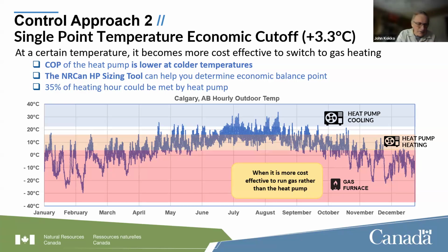we were talking about this a little before the seminar started, but Alberta has very complicated energy pricing, and it changes continuously. So I've tried to use an average over the year and said the price of electricity is about 2.5 or a little bit more, 2.8 times more than gas on average over the year. So that means once my COP drops below, let's call it 2.5, my electric use with a heat pump and a COP of 2.5 is going to be more expensive than using gas.